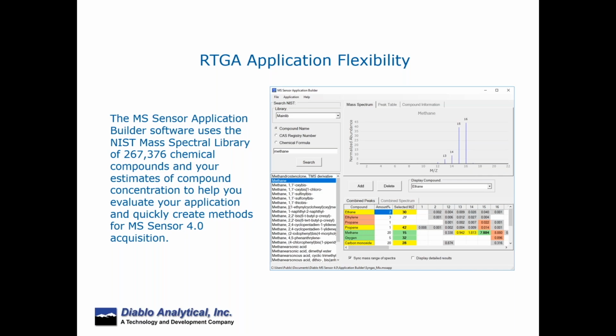And you can see that we can type in, for example, methane in the search bar. And the fragmentation pattern that's shown there is for methane. And then we can add components sequentially to our method. So in the lower right corner of the table, you can see the ethane, ethylene, propane, propylene, and so on. Those are the components that we've added, and we've specified the approximate concentration. The software then goes out and looks at the ions that are present for a particular component. In this case, we're showing the methane.